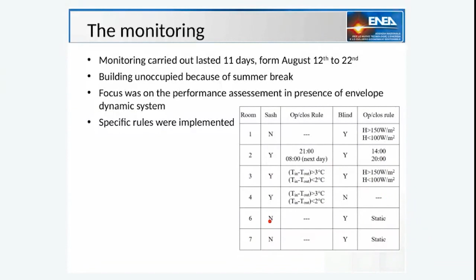In room 2, we have night opening of the windows to provide night ventilation according to a simple hourly schedule. And again, we had an hourly schedule also for the blind activation. In room 3, there was a control based on physical parameters. For the night ventilation, it was the difference between the indoor and the outdoor temperature, so that it was possible to ventilate the room only when the outside temperature was significantly lower than the indoor one. While for the solar irradiation, we kept the same rule as in room 1. For room 4, as an example, we only studied the impact of the night ventilation without any rule on the solar irradiation. The remaining rooms of the Living Lab had no installed advanced windows, so we have them in a free-floating condition without any shading and without any night ventilation.